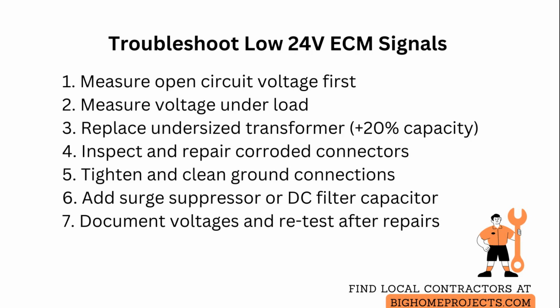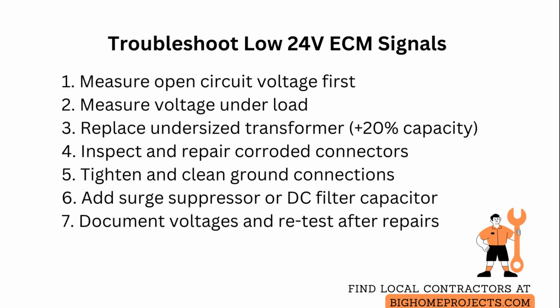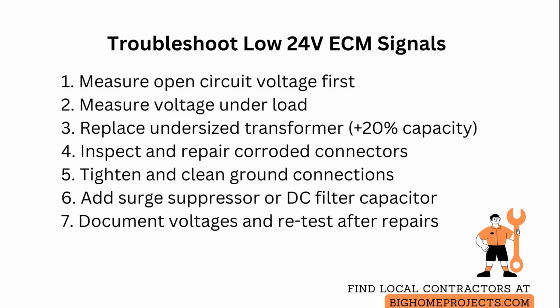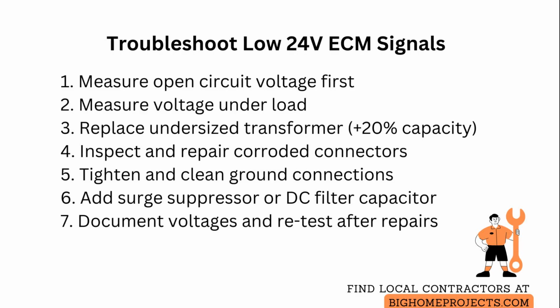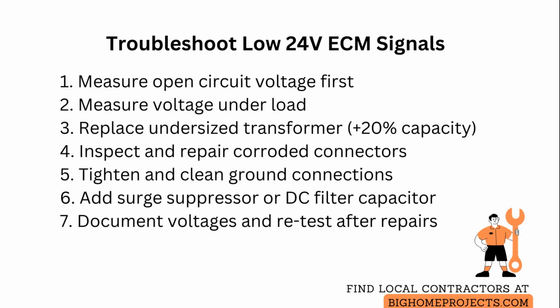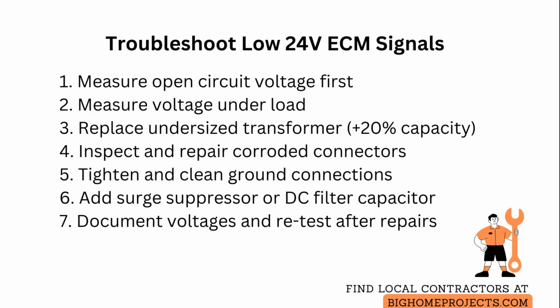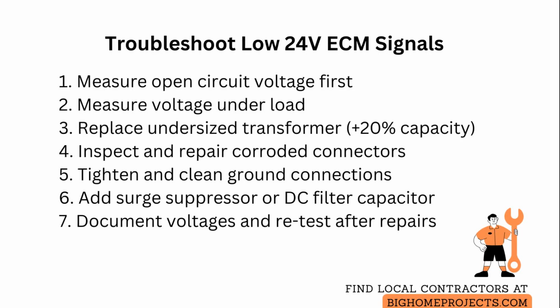If you see fluctuating voltage that correlates to other load switching, add a small surge suppressor or a 24-volt direct current filter capacitor near the module to smooth transient dips, selecting capacitance appropriate to the module inrush and ripple characteristics. Document the measured voltages and conditions, and then retest after each repair so you confirm the fault is cleared and not just temporarily masked.